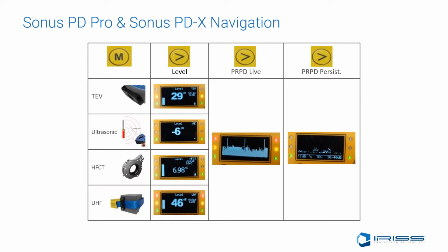These screens quickly allow the operator to identify the exact source of the anomaly and run a comparison method between multiple cabinets to see which one has a higher intensity level. This allows the inspector to quickly target an area of concern and make a call on the asset's health.